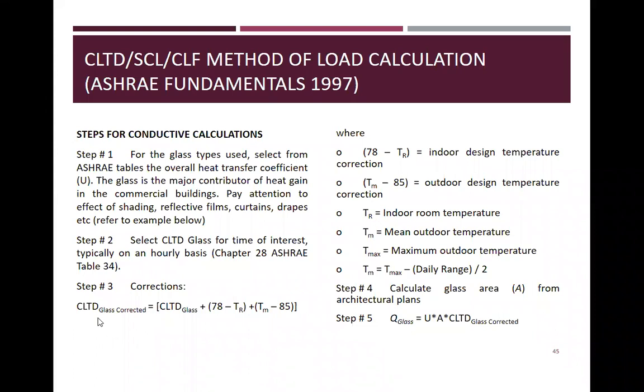So, CLTD glass corrected is CLTD glass plus 78 minus T sub R plus T sub M minus 85, where 78 minus T sub R is the indoor design temperature correction. T sub M minus 85 is the outdoor design temperature correction. T sub R is the indoor room temperature. T sub M is the mean outdoor temperature. T sub max is the maximum outdoor temperature. So T sub M is equal to T max minus daily range over 2.